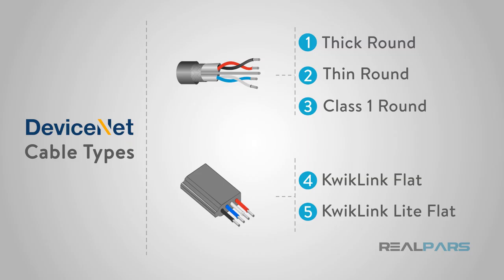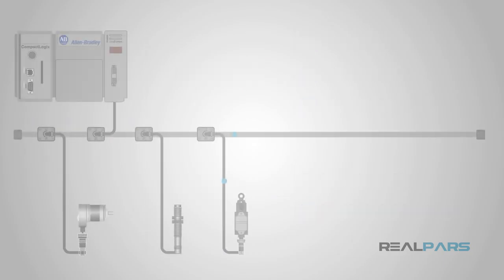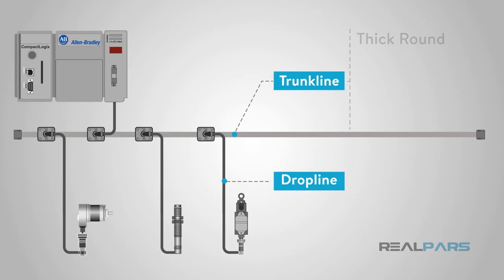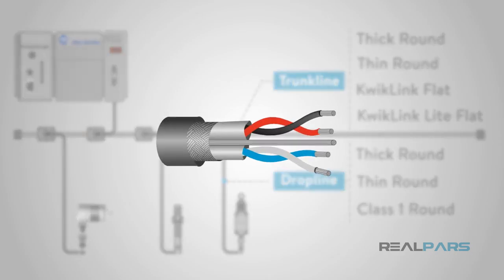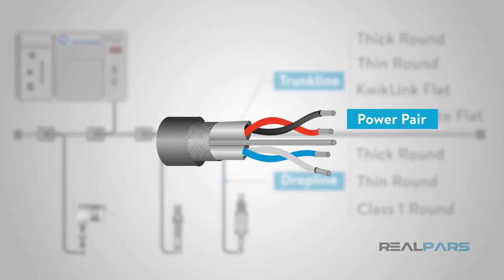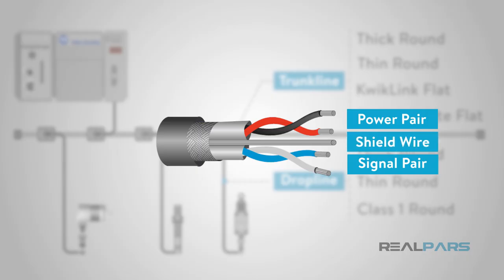Which one you choose is determined by the distances and physical limitations of your application. You can use the round thick or thin cable for either trunk or drop lines. The flat is used for trunk lines and the class 1 drop cable is used for drops. They all use twisted pairs of wire — one pair for the 24-volt DC power and one pair for the signal. There is also a shield wire used in the grounding process.